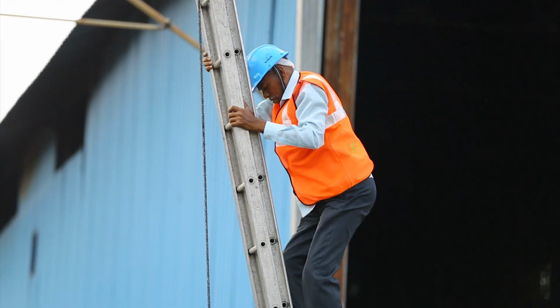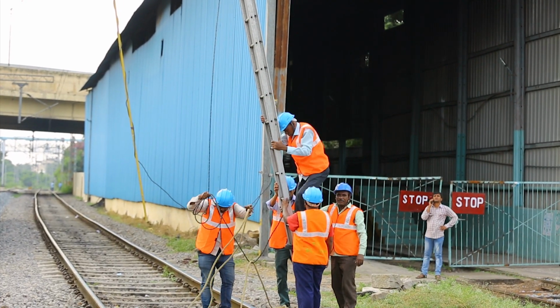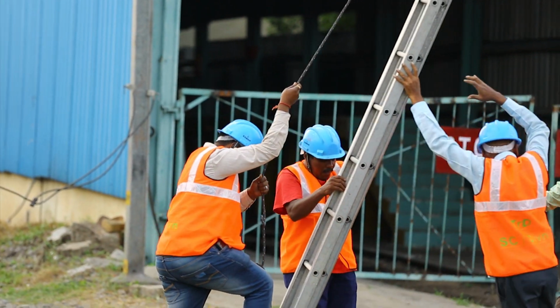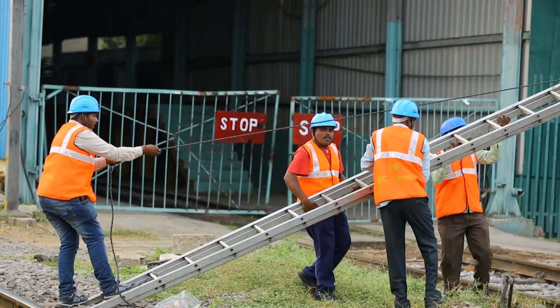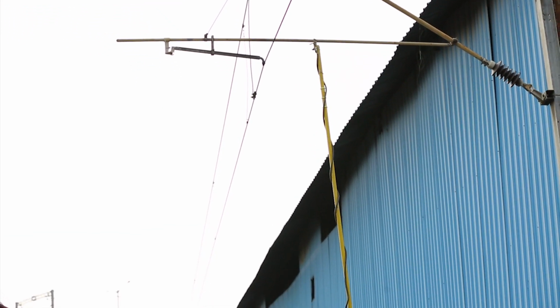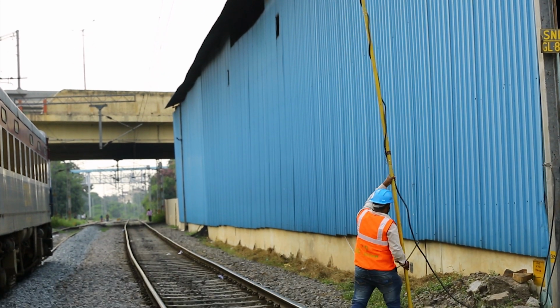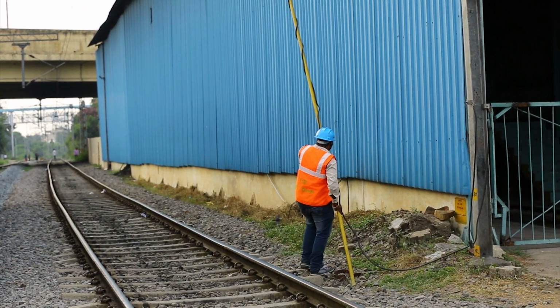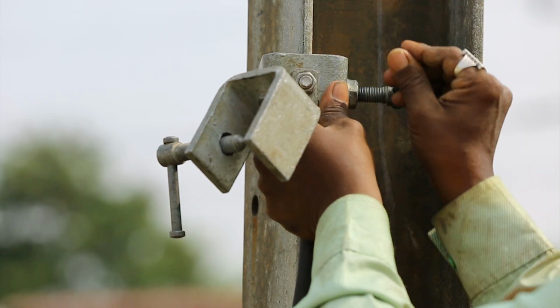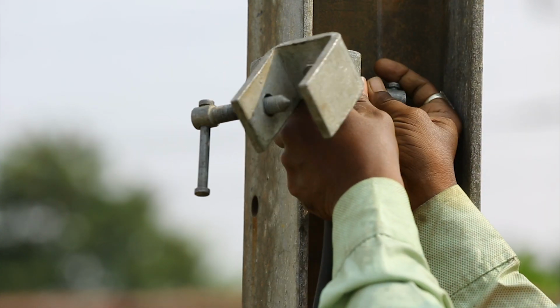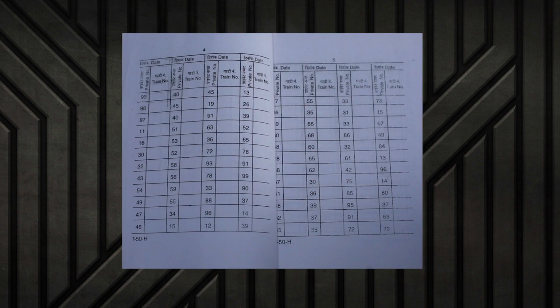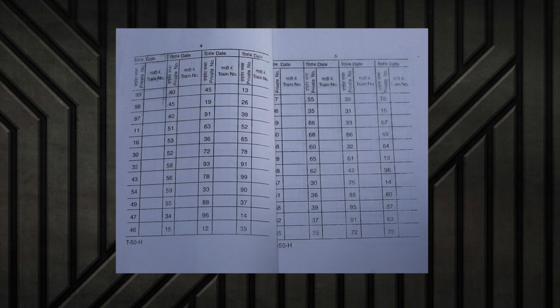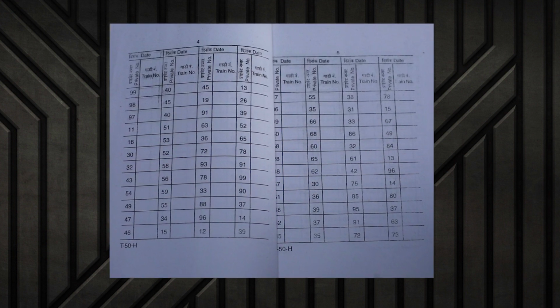Once the work in OHE is completed, then all the men should get down and all the material used is to be shifted away from the OHE. For removing the earthing, first remove the hook of discharge rod on the OHE and then the clamp fixed to the rail or mast. All messages relating to shutdown and restoration of power supply, permits to work, etc. issued over the telephone shall invariably be supported by exchange of private numbers and repeated twice.